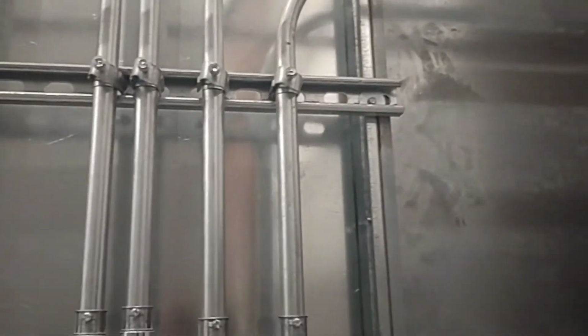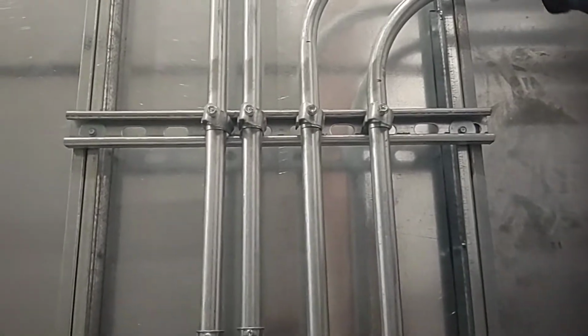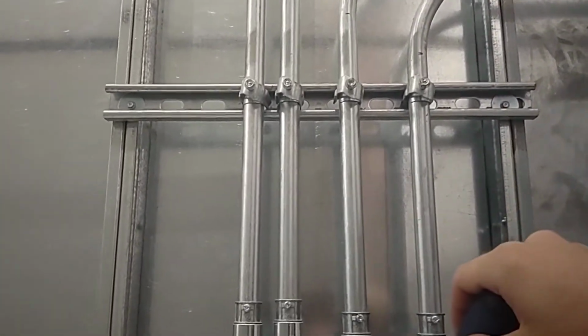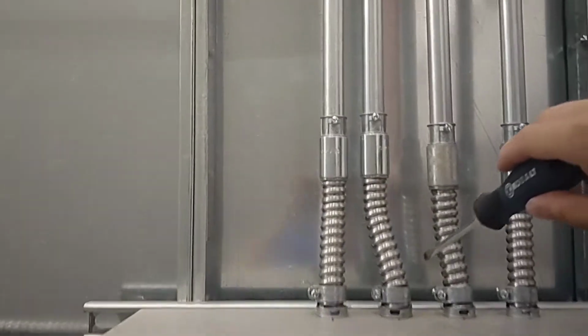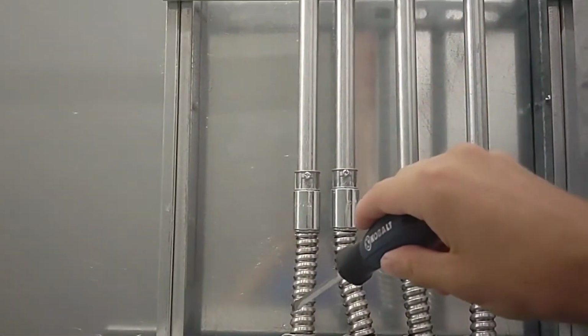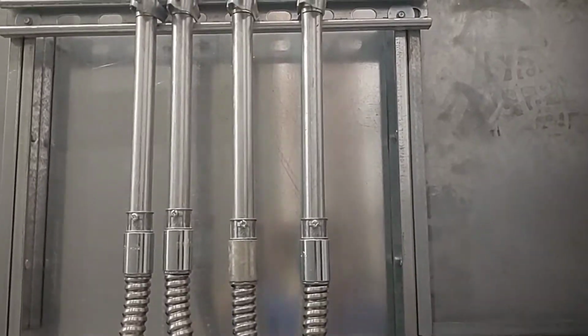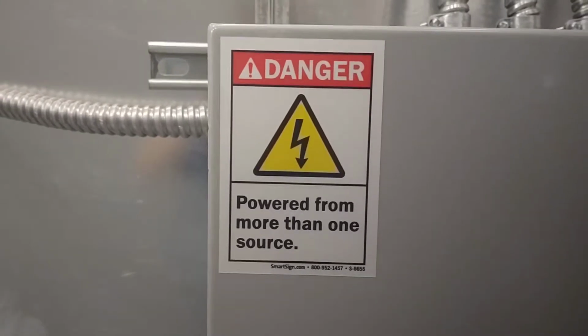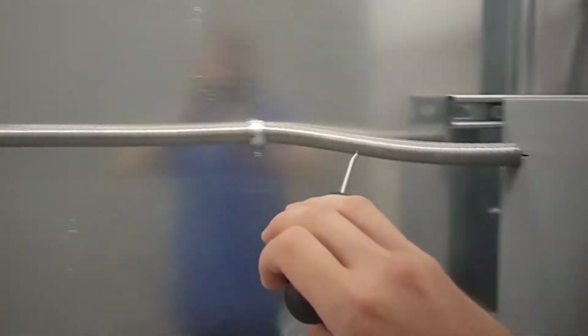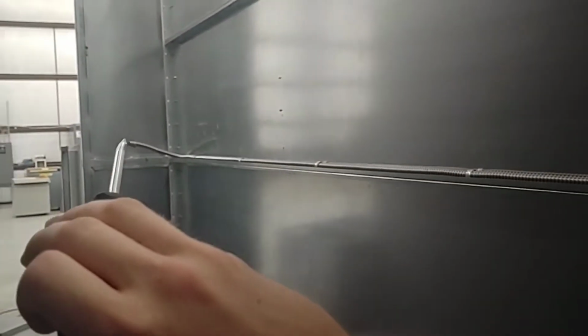So we had our electricians come and they ran us some power. This here is an air line, and so we've got 480 coming in on one, 120 coming in on one. That's for our lighting, and then we've got 120 going out to our lighting and 480 going out to our fan motor. And so very important to label your panels correctly. Additionally, this conduit right here goes up to our pilot controls.